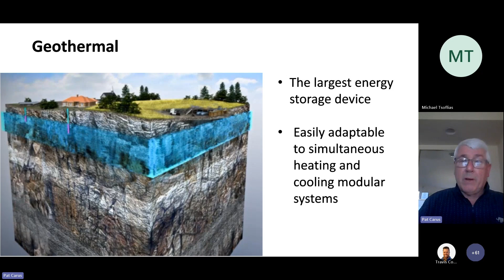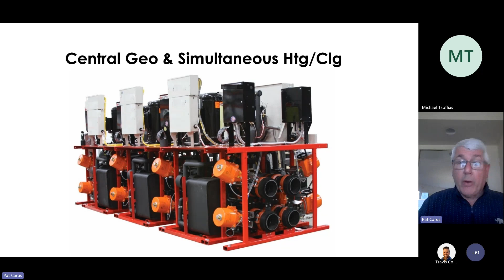This machine you saw earlier is the VME machine, and this is the same kind of heating or cooling or simultaneous operation. Again, understanding your load - for those who know the Multistack product line, what you see here is essentially our original foundational piece of equipment, the modular chillers, with a set of valving introduced at different locations. It doesn't have to look like that; it can have fewer valves depending on how well you know your load. But this is how it would work in this particular situation.